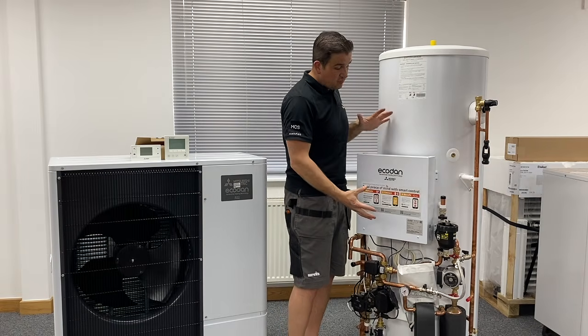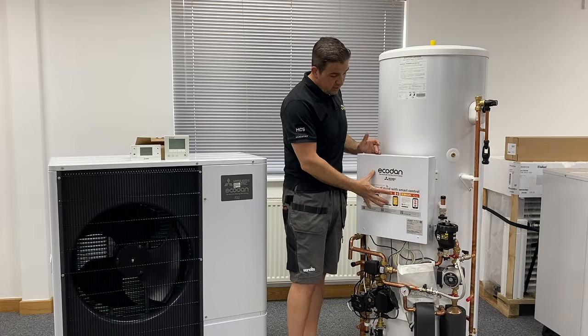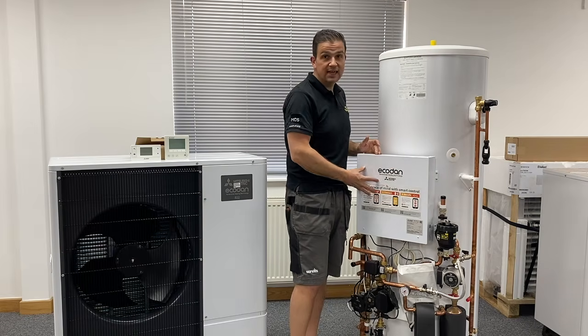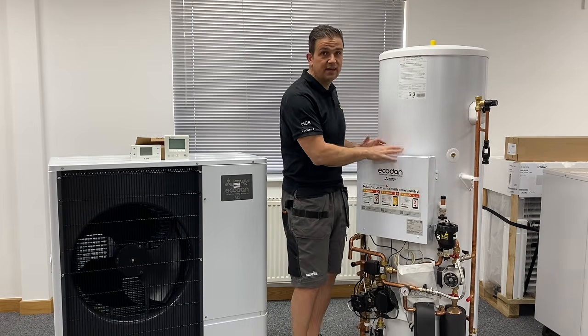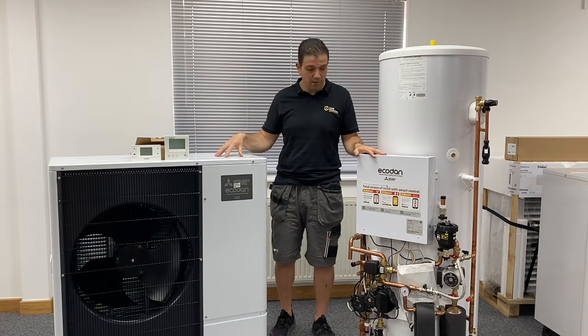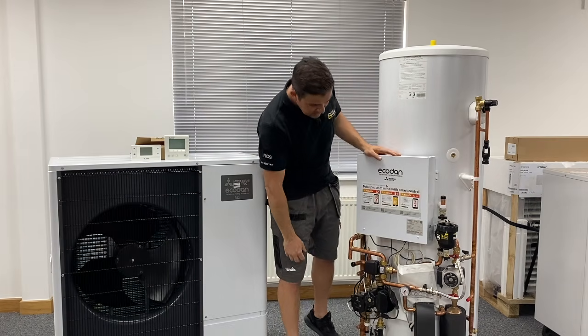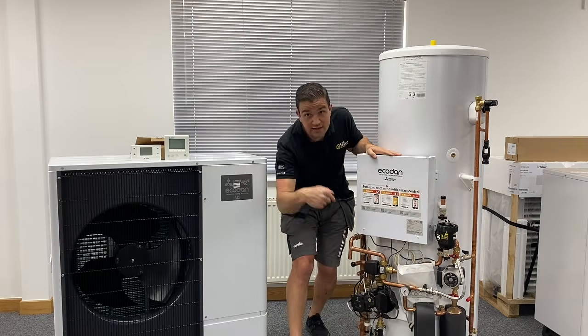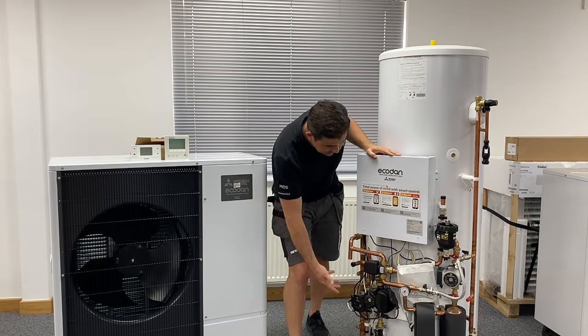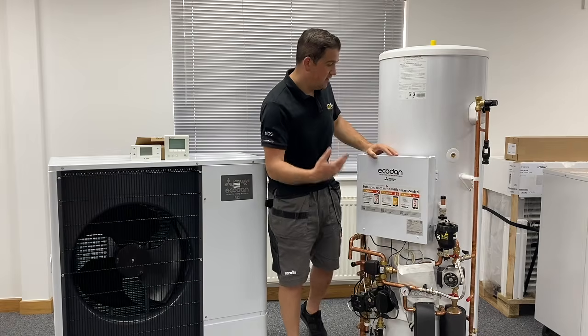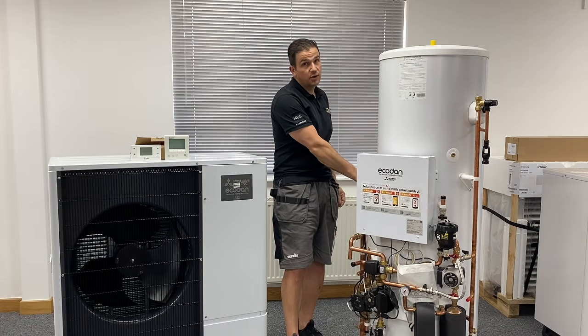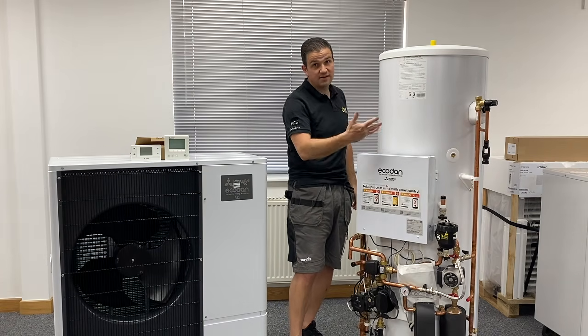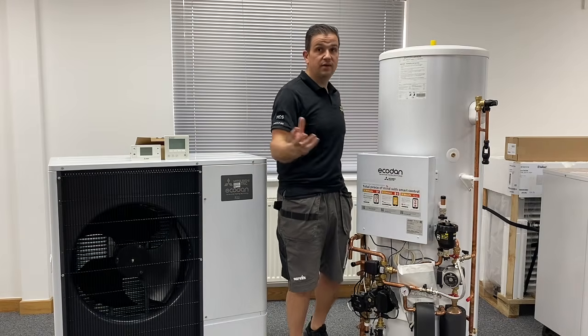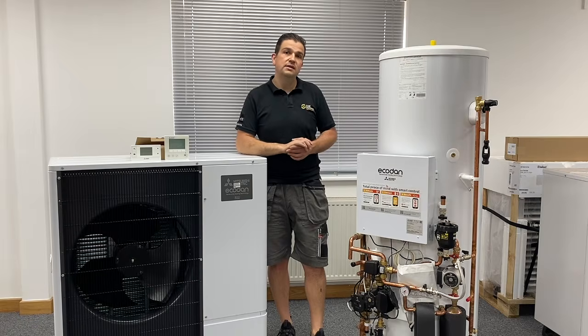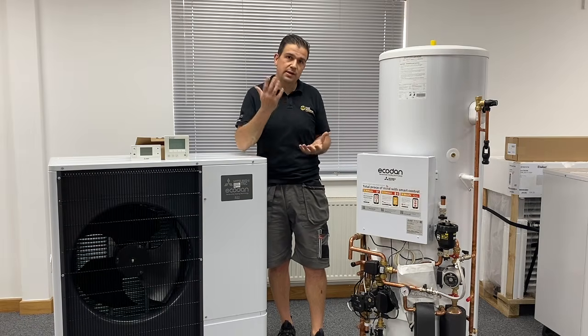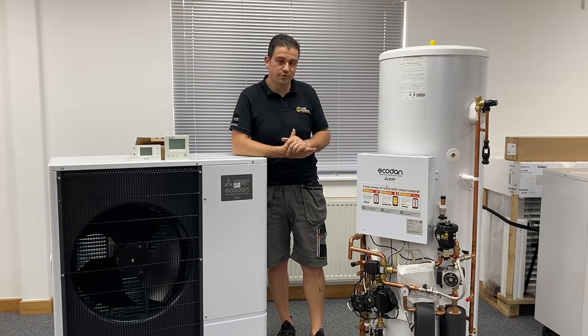And then you'll get certain elements that will come with the package, i.e. this is the FTC, this is your control unit, this is the interface that basically will talk to the heat pump and a couple of other ancillaries. There's a flow sensor down here, and we'll look at this in more detail and go through it. There's a flow sensor, and then you'll need a thermostat, which will be a sensor that will go into the pocket of a cylinder to enable it to tell the heat pump how much hot water is available inside the cylinder at that time, just so it can start producing and regenerating that hot water if necessary.